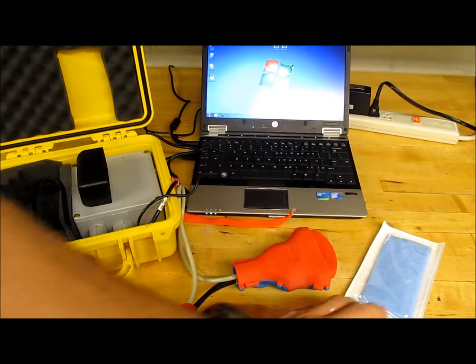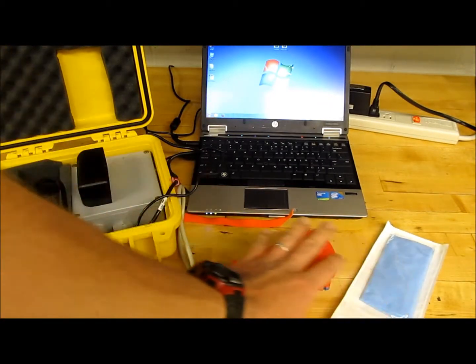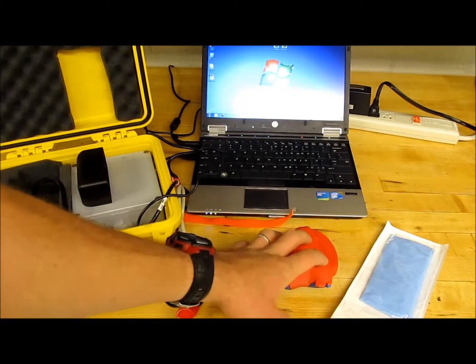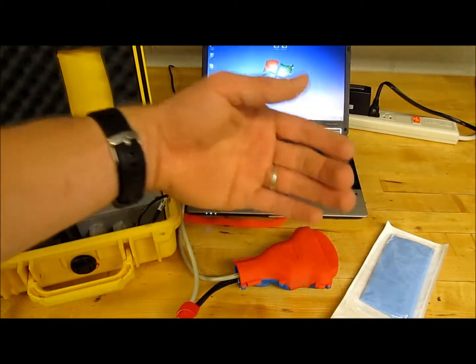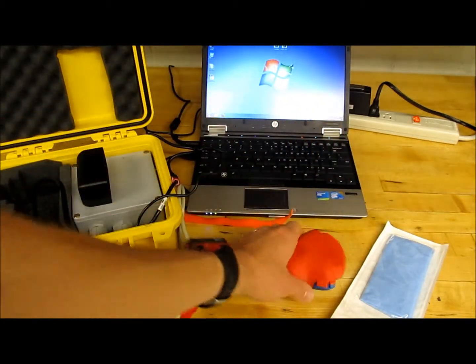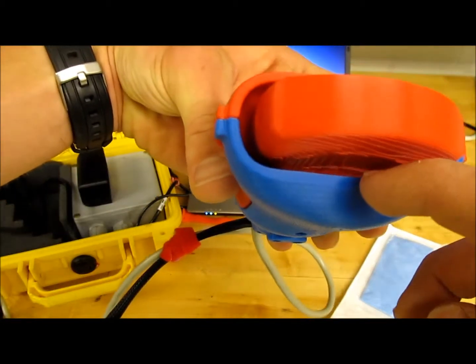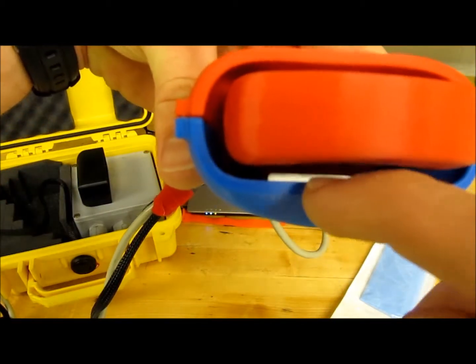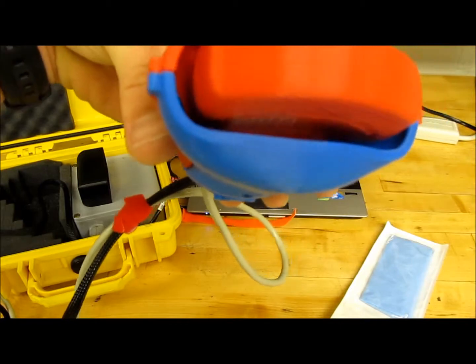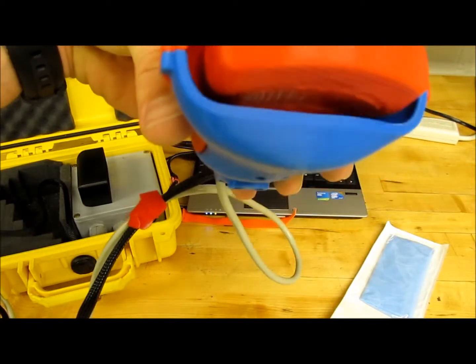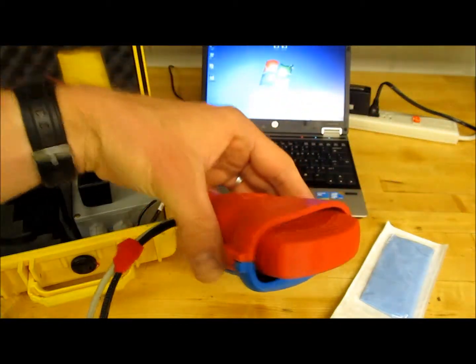The next step is to attach the probe cover to the actual force measuring device. The reason we want to do that, in addition to sterility, is that there's a force sensor a small distance beyond this shiny aluminum piece here, and we don't want to get any ultrasound gel into the force sensor itself. That would cause it to give inaccurate readings.